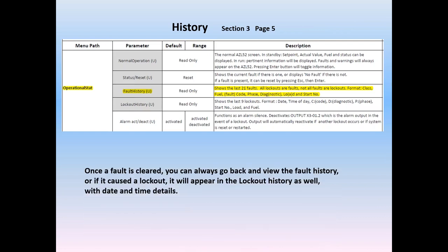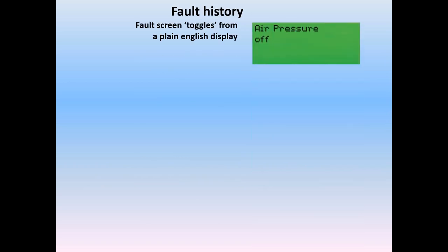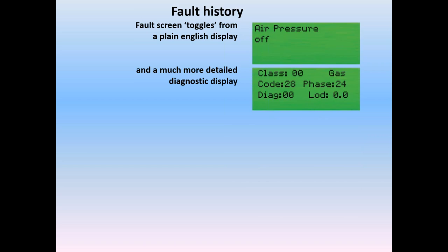Once you clear that fault, you can always go back and view it in the fault history. Or if the fault caused an actual lockout, then you can see it in the lockout history as well, and that will have date and time details specifically of when the fault occurred. When you go back to the fault history and look at it, the fault screen is going to toggle again from the plain English display to a much more detailed diagnostic display. Pressing enter will halt the screen on either of the two toggles so that you can work on the unit.